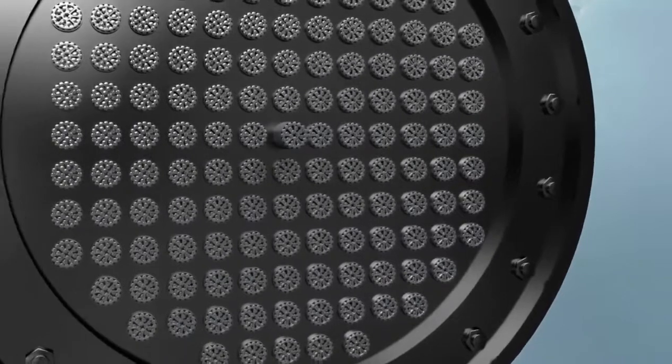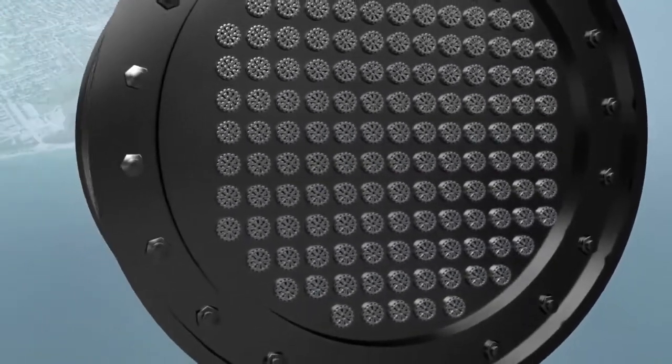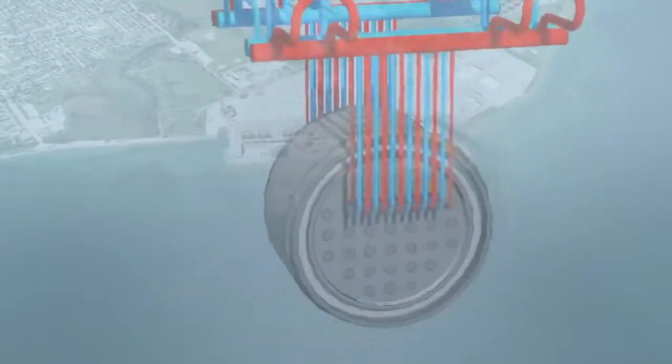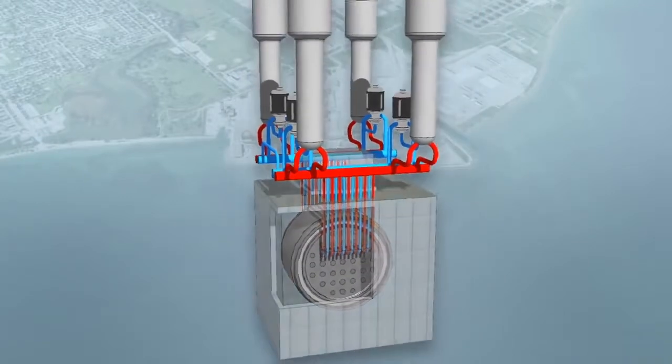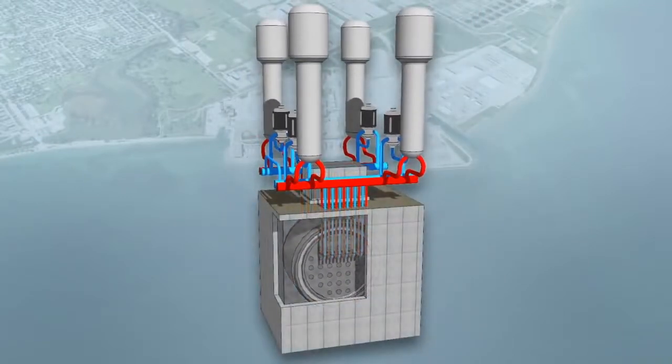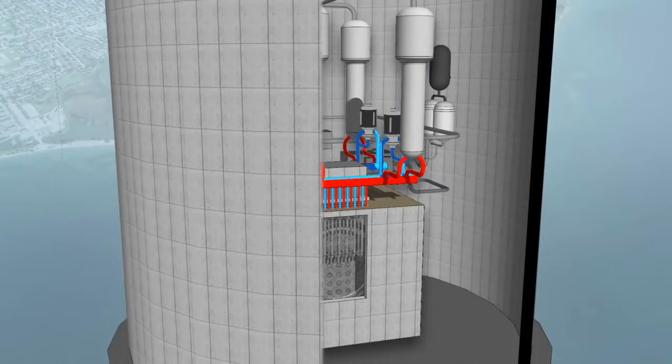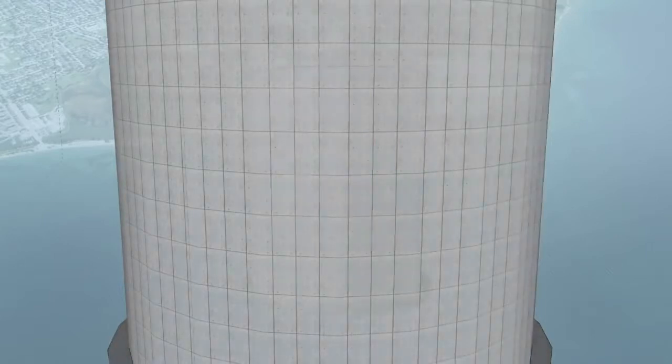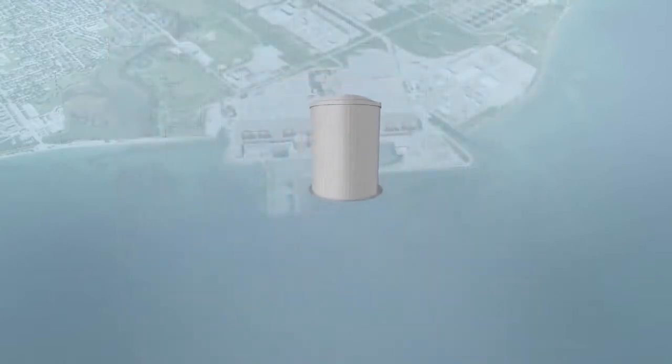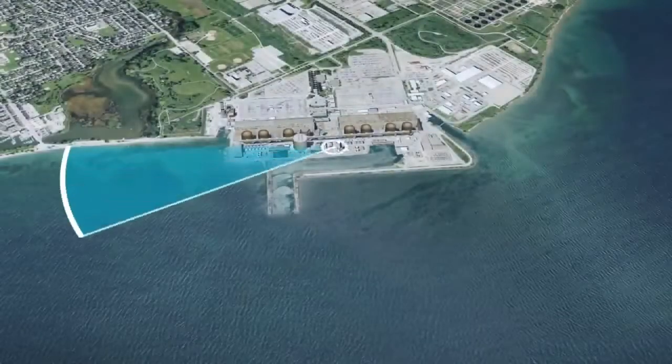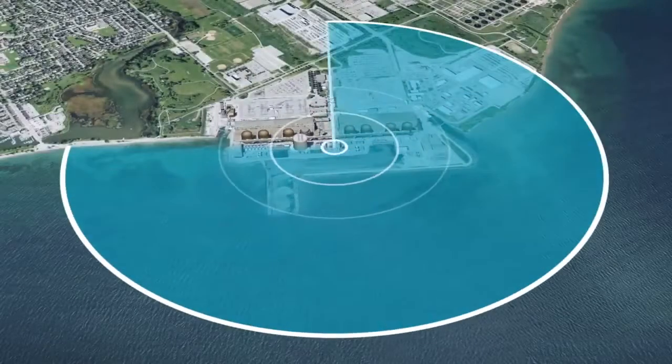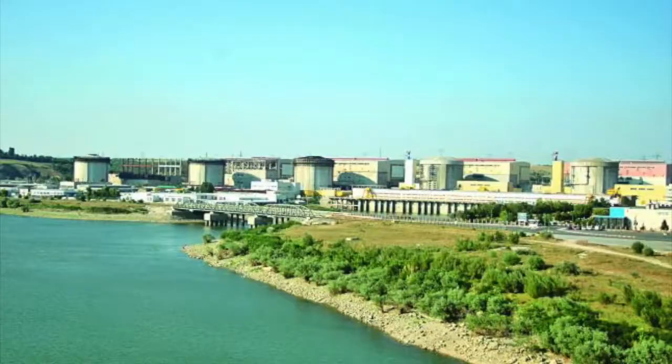The pressure tubes are contained inside a metal tank, called the calandria, which itself is contained inside a thick vault made of reinforced concrete. The fourth layer of containment is the building that houses and protects the reactor. The walls of the reactor building are made of at least one meter of reinforced concrete. The reactor building is surrounded by a one kilometer exclusion or buffer zone.